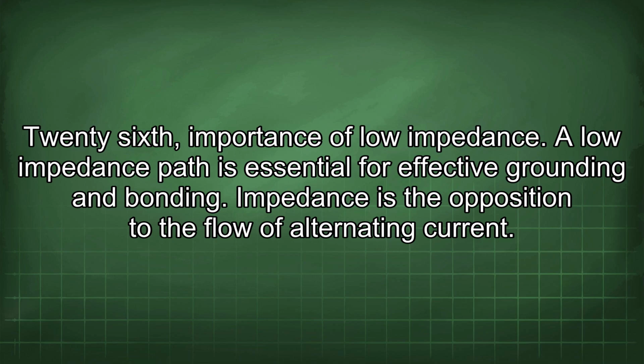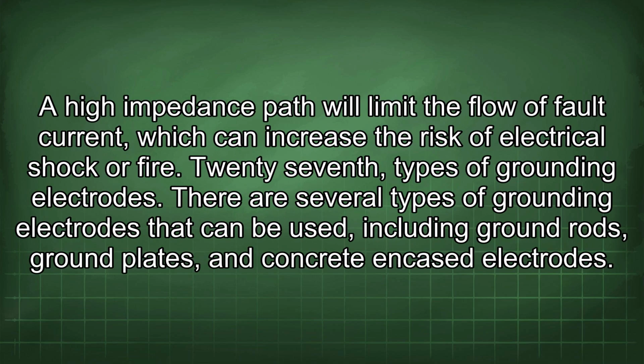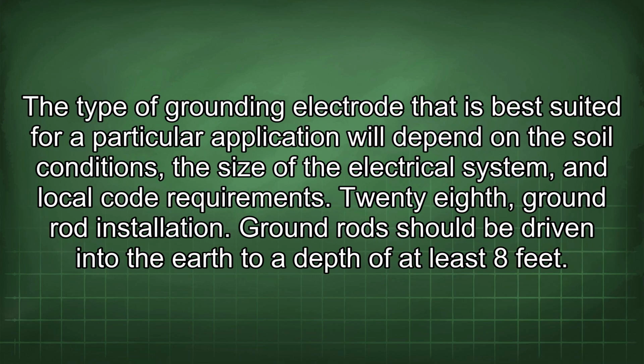A low impedance path is essential for effective grounding and bonding. Impedance is the opposition to the flow of alternating current. A high impedance path will limit the flow of fault current, which can increase the risk of electrical shock or fire. 27th, types of grounding electrodes. There are several types of grounding electrodes that can be used, including ground rods, ground plates, and concrete encased electrodes. The type of grounding electrode that is best suited for a particular application will depend on the soil conditions, the size of the electrical system, and local code requirements.